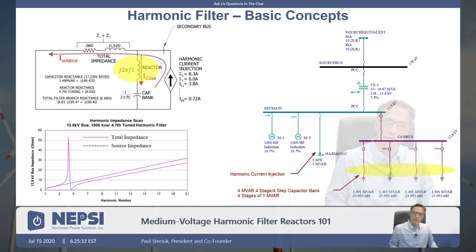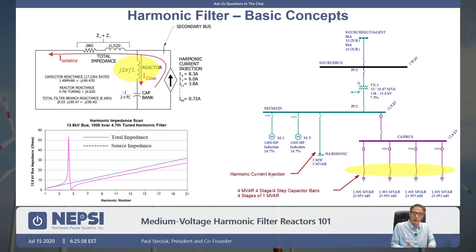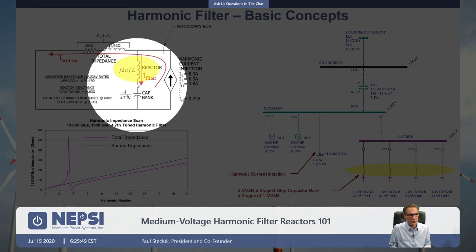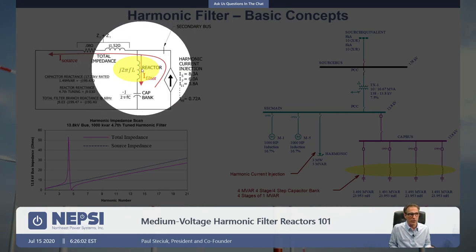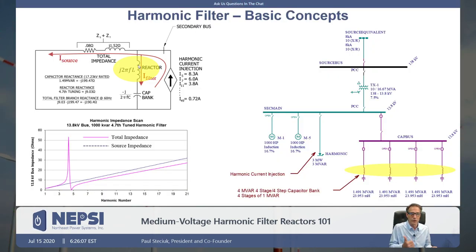Let's do some harmonic filter basics first and talk about what a harmonic filter is. A harmonic filter consists of a capacitor and a reactor — the most basic notched harmonic filter system — but there's also sometimes a high-pass resistor. So we have resistor, capacitor, reactor. Today we're talking about what's shaded in yellow: the actual reactor. In some cases this might be iron core or air core. Iron core is used in metal closed systems; air core is used in open air systems.